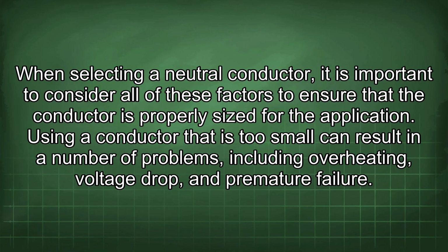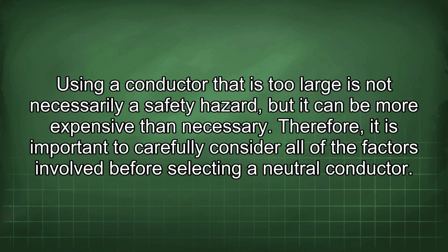When selecting a neutral conductor, it is important to consider all of these factors to ensure that the conductor is properly sized for the application. Using a conductor that is too small can result in a number of problems, including overheating, voltage drop, and premature failure. Using a conductor that is too large is not necessarily a safety hazard, but it can be more expensive than necessary. Therefore, it is important to carefully consider all of the factors involved before selecting a neutral conductor.